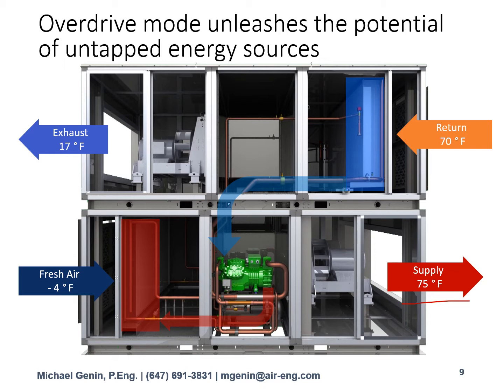Let's say you have a central gas heating plant? Well, depending on the cost of gas, it's typically about 3 or 4 times less expensive to heat with gas than electricity, so a ratio of about 4 to 1. Well, the active heat recovery has a COP of 7. So by running it harder, you can actually offload some of that energy from your natural gas plant and put it on your ventilation unit, resulting in both cost and greenhouse gas emission reductions.